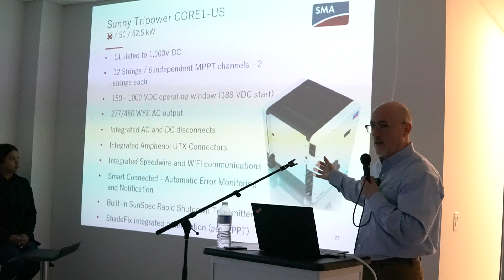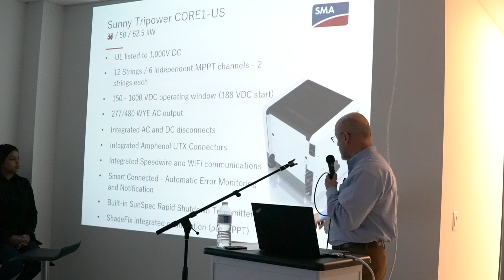The strength of this product is that it's got a lot of its balance of system functionality standard in the inverter itself. It has a DC disconnect, this being the DC bulkhead right here. On the other side, you've got an AC disconnect on it. This is the DC bulkhead. These are Amphenol UTX connectors. By the way, we ship the mating connectors in the parts bag for this, so they're included with it.